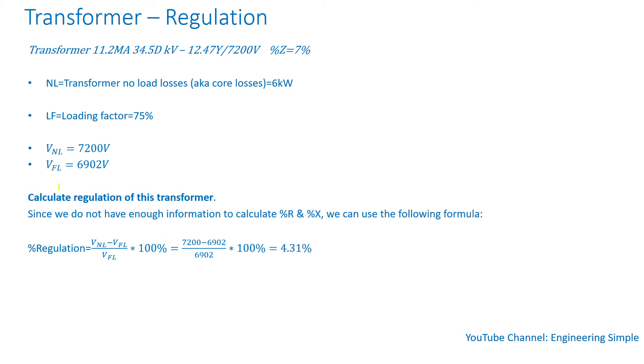From this example, the no load voltage is 7,200 and the full load voltage is 6,902 divided by 6,902 times 100%. So it's 4.31%.